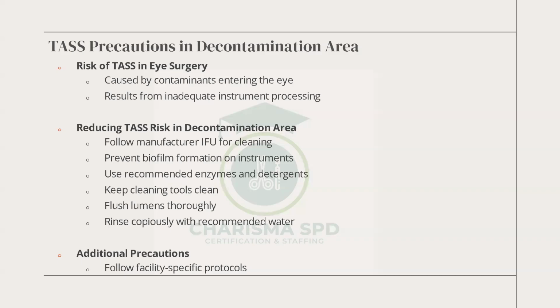It results from inadequate instrument processing, which means it's our fault, right? We didn't process it right. So to reduce that, we have to follow the IFU, which I told you, the information for use, the manufacturer's recommended use. Use that to clean it.